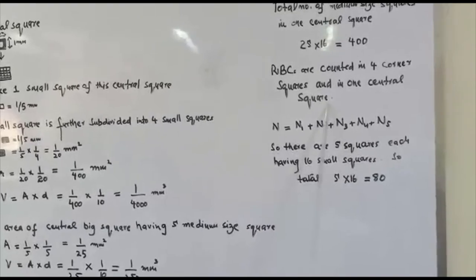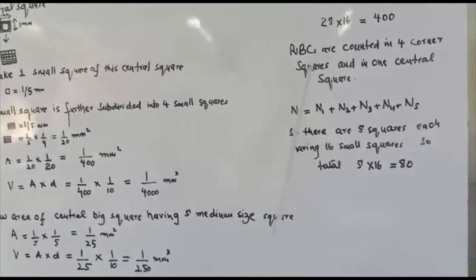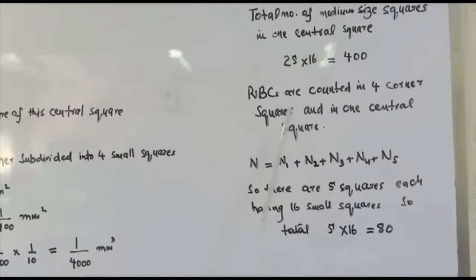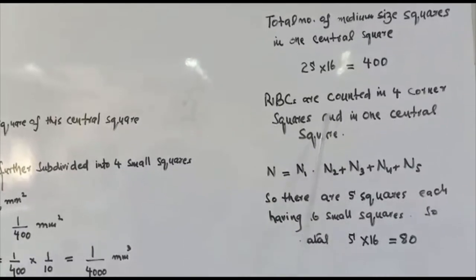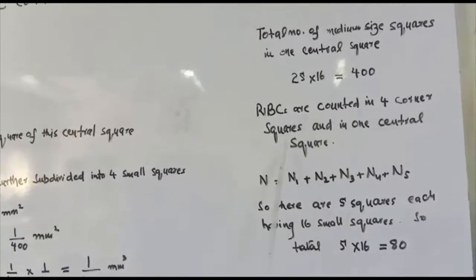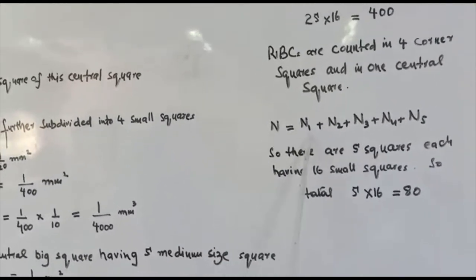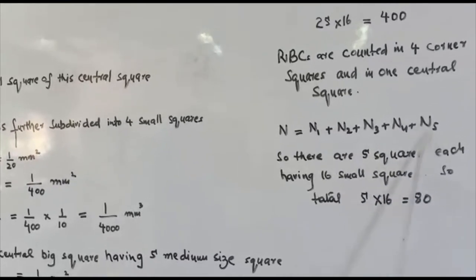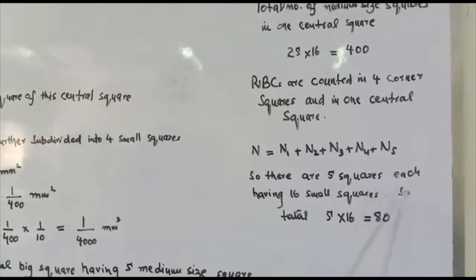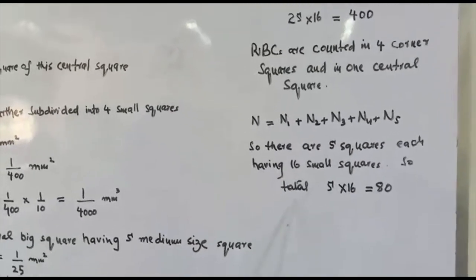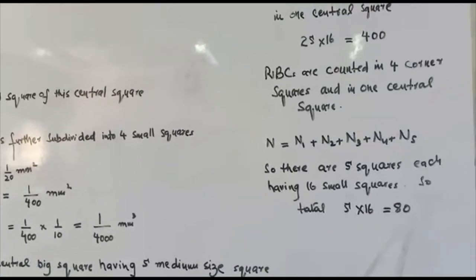RBCs are counted in the four corner squares and in one central square. The total N = N1 + N2 + N3 + N4 + N5. There are five squares each having sixteen small squares, so the total number of squares in which we count is 16 × 5 = 80.